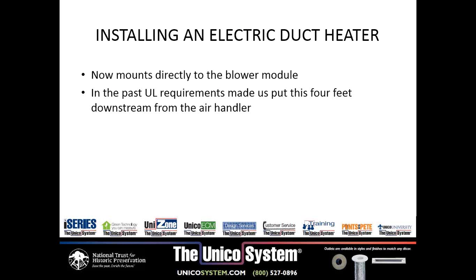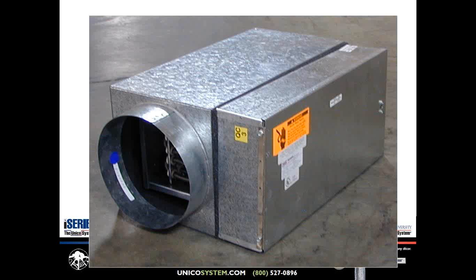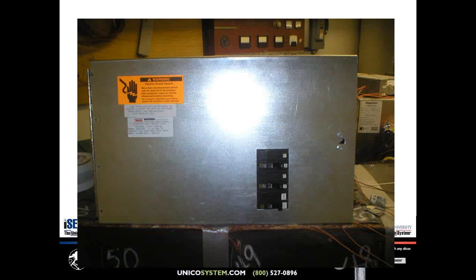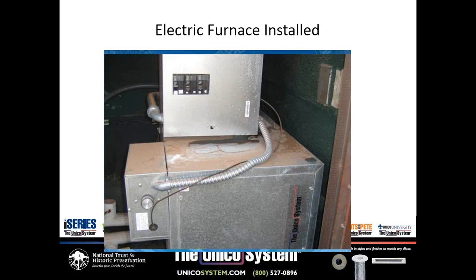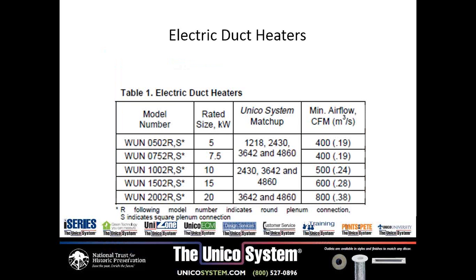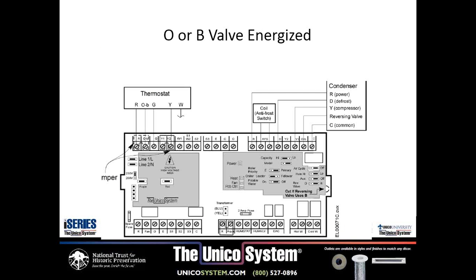The electric duct heaters mount directly to the blower. This is what they look like. They include the breakers. And this is a very simple installation. This is our 10 kW. We make these from 2.5 up to 20 kW. We only use the 20 kW on the larger systems, the 3642 and the 4860s.